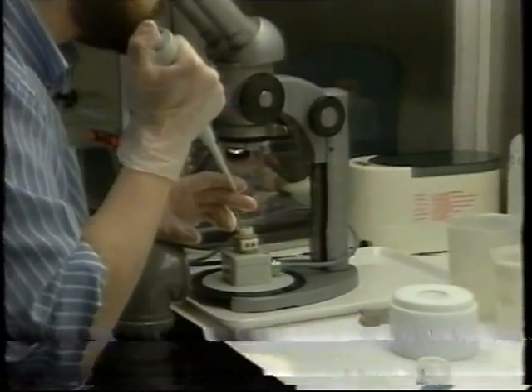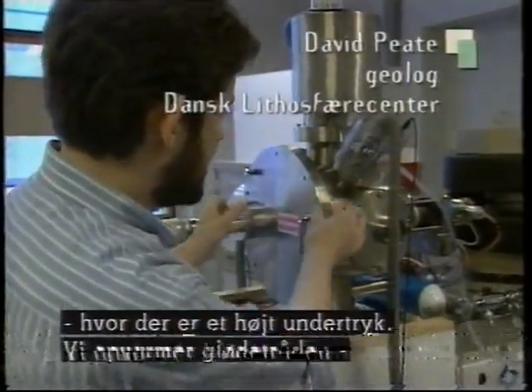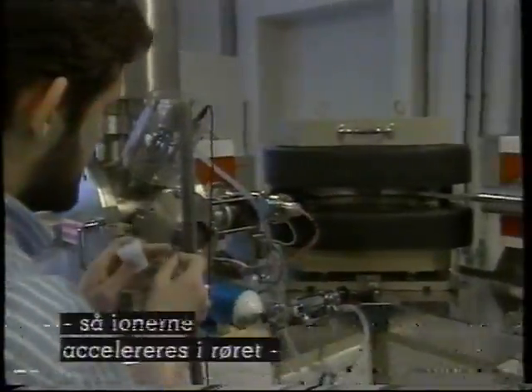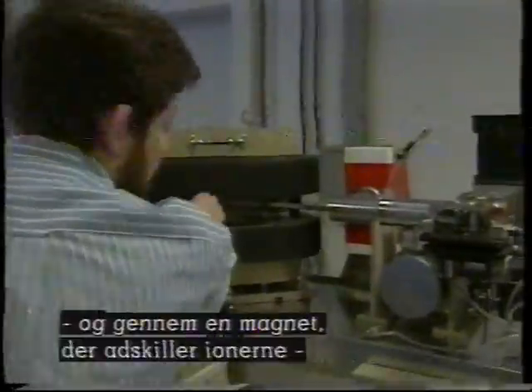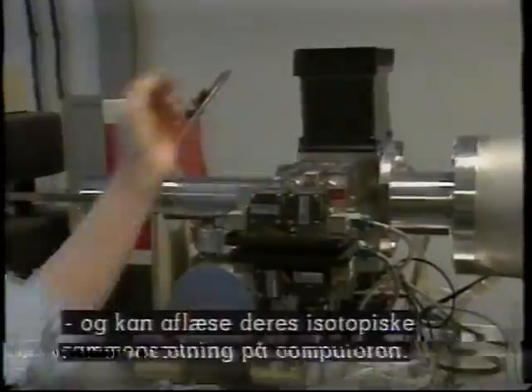Analyserne foregår i et ultra-rent laboratorium her på Geologisk Institut på Københavns Universitet. The sample which we have isolated in chemistry, we load onto the thin filament, as we have set, and we load it into the mass spectrometer here. The whole steel tube is in a very high vacuum. We heat the filament up with a current, it gets warm, and it ionizes the element. The whole flight tube is at high potential, 10,000 volts. So these ions are accelerated in the tube, and we sort them by mass. The heavier ions go along more, the lighter ions become deflected more. And then we collect the ions here, and we can read the details on the computer, and it shows us the composition of the element.